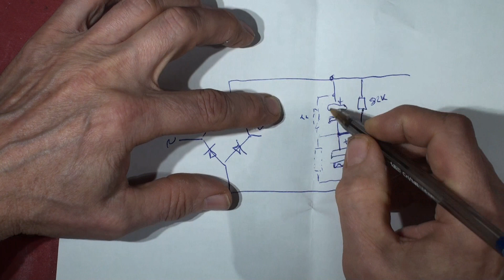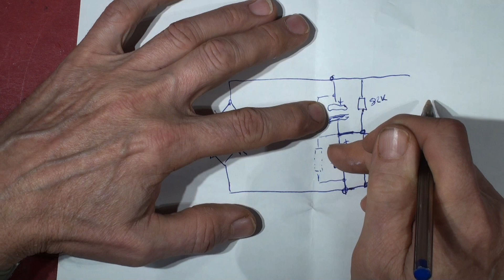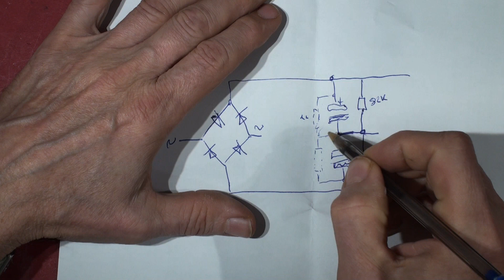Now if one capacitor has got a higher leakage current than the other, it can start to change the actual voltage. Their midpoint voltage can drift, especially if you've got some sort of other DC current supply drawing off this. It will take them a long way out of whack.